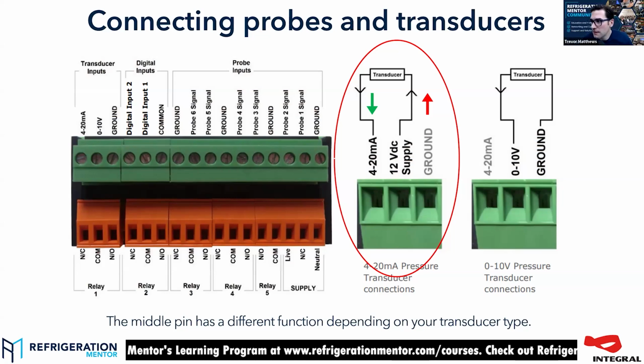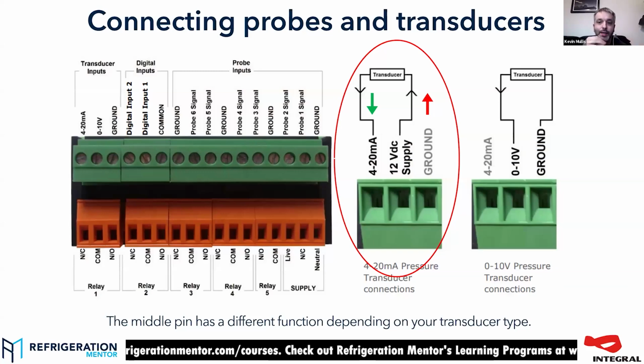The 12 volt supply and then the 4 to 20 milliamp. Exactly. So when you configure that controller to trans MA, transducer milliamps, that's what it'll expect it to be wired as. The reason I've drawn attention to it is that if you look on the drawing for the main controller, the middle pin says 0 to 10 volt. But that only applies if you're bringing it a 0 to 10 volt input for your pressure reading, which isn't that common a thing to do from a transducer. So people look at the plug and they're like, this is a bit confusing because that says it's an input. Yeah. So it's important to know that that pin does something different depending on how you've got it configured. So that's the main bit with the transducer.